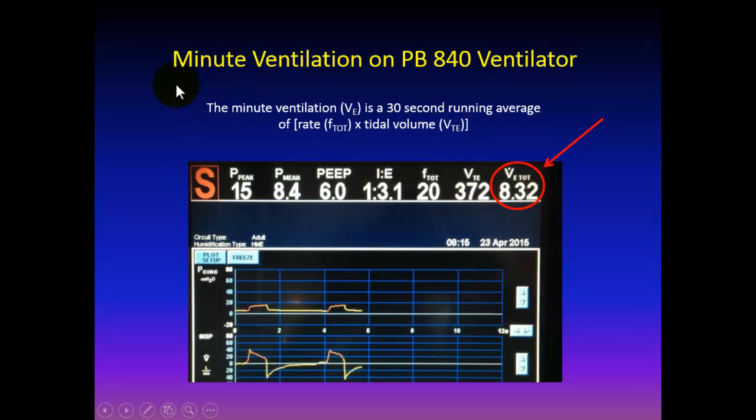We monitor minute ventilation continuously on our ventilator, the Puritan Bennett 840. It is the product of frequency and tidal volume. In this example, 8.3 liters is slightly higher than 7.4 liters because one is a running average over the last 15 to 30 seconds while the other is an instantaneous value.